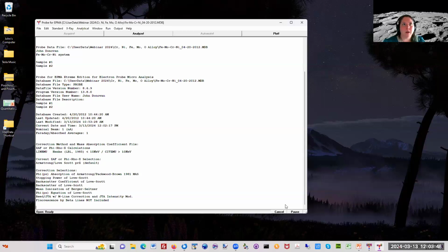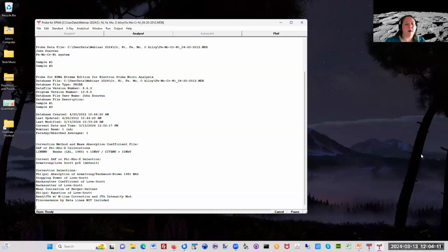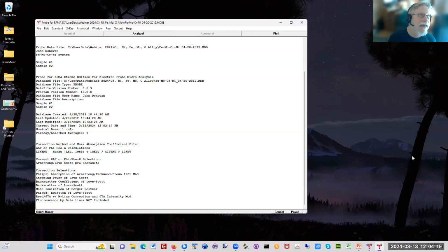Whereas if I run a spectrometer scan, I can in the dialog just with a right mouse click record the new value into the setup. But if you just select the maximum of the PHA, that doesn't help you, because you still need to adjust the gain or the bias. I think the idea is that if you run a voltage scan, a bias scan instead. Oh, I think that's probably more the JEOL people talking than the Cameca, but okay.